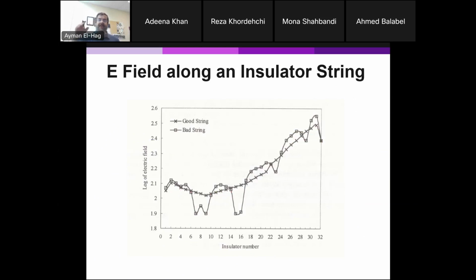You will find that whenever there is a defective insulator, the electric field will drop. Okay, drop. Why? Because there's an internal short circuit. Could be partial, could be complete. So that is a good string. This one is a good string. You see here, the field is somewhat uniform. There is no dipping, so there is no damage in the insulators. But you look here, there is some dipping happening at these points.